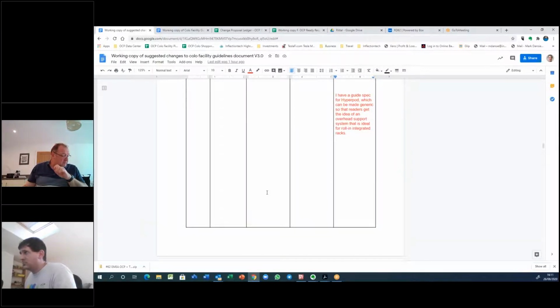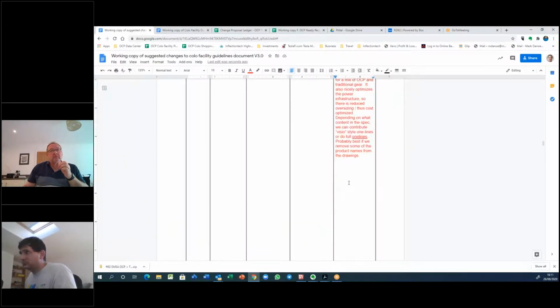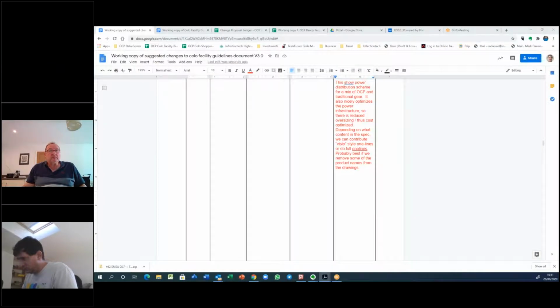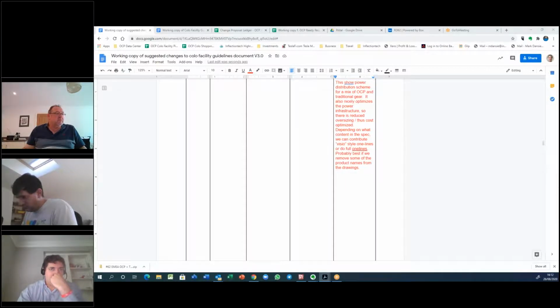Yeah, and to add on that, it might be a bit dated, but the white paper that you referenced was our cost analysis of what that looks like, I believe. With regards to removing the centralized UPS and putting batteries in the rack, it all depends on how much stranded capacity you end up having. If there's homogeneity in the rack loads, you're in really good shape. If it's going to be highly variable, then you could overshoot and spend too much on the batteries in the rack. But that's a publicly available white paper. This could be a starting point. Okay, I'll share the link to the white paper after the call.